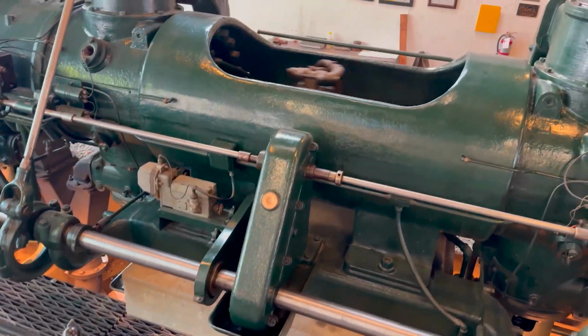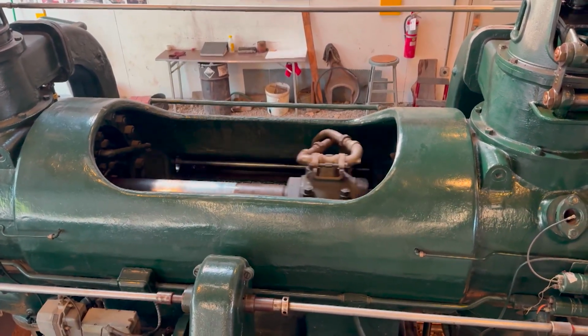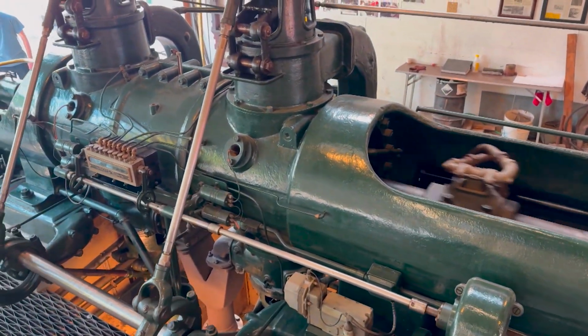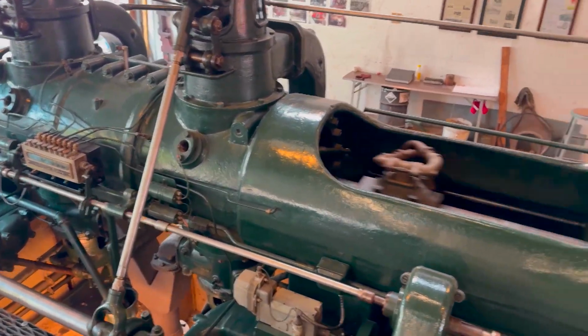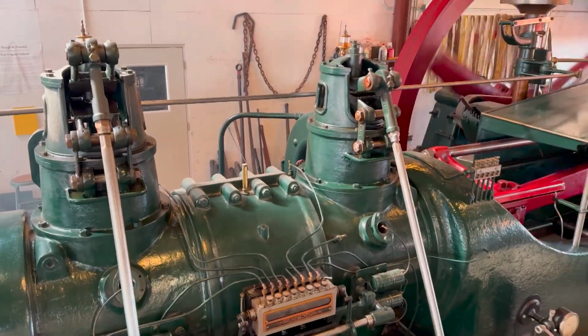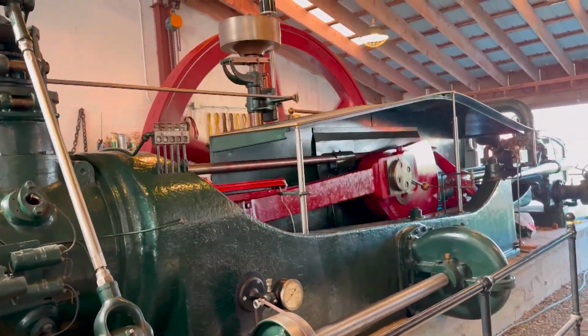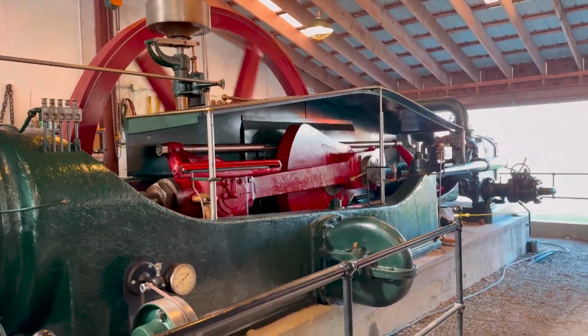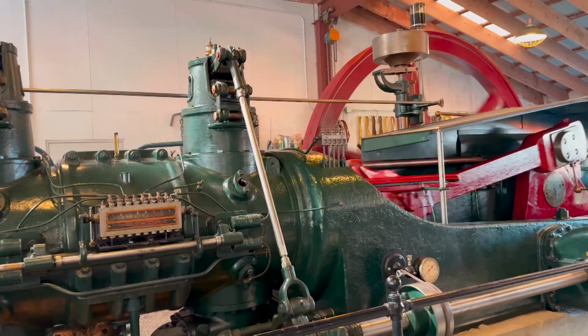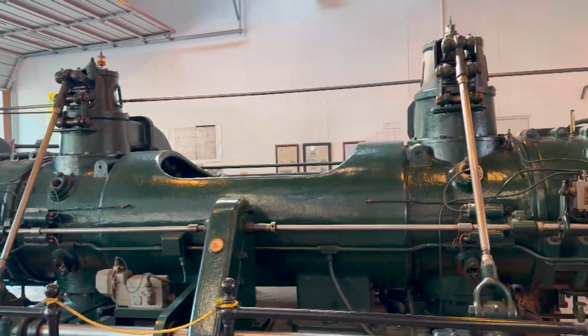The piping that you saw in the center is part of the water cooling system in here. There's a water cooling system that supplies around the exhaust valves, goes up around the cylinders, and then goes out to be recirculated. Then there's another system that actually goes through the cylinder heads on this end, then goes through the pipes in the middle, and then through that piston and out, and then those cylinder heads on that end come through the center here and go through this piston and out. And the pistons are water cooled while they're running.